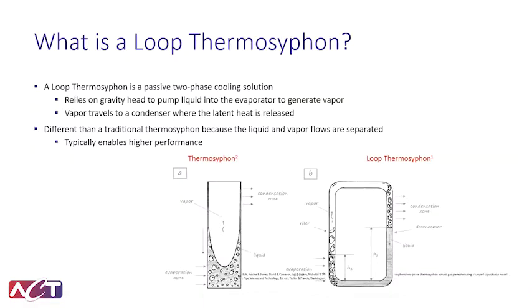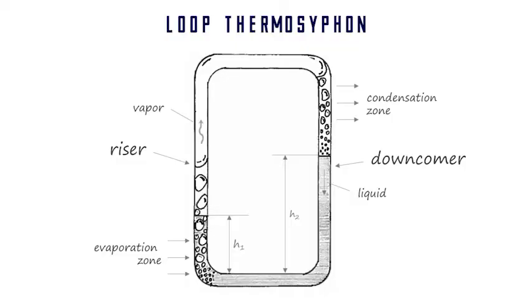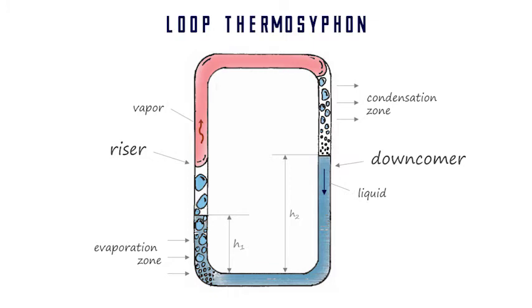A loop thermosiphon operates on the same principles, but we separate the liquid and vapor flows in more of a loop fashion, as the name suggests. If you look on the right side image, we utilize the height of the liquid to drive the loop. This pressure head pushes liquid into the evaporator section. You boil all the liquid in the evaporator and it creates voids inside of the flow. Those voids reduce the density of the fluid and that allows the liquid to displace the flow all the way around the loop. The two-phase mixture travels up to a condenser where you can remove some heat, condense the liquid back to its form, and then it falls into a liquid column to continue the loop.